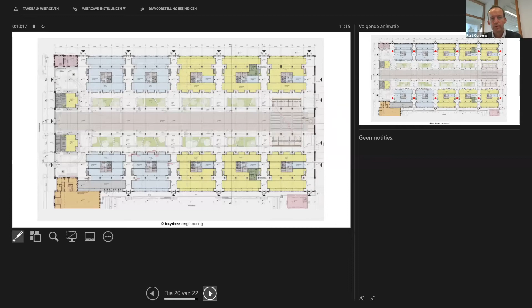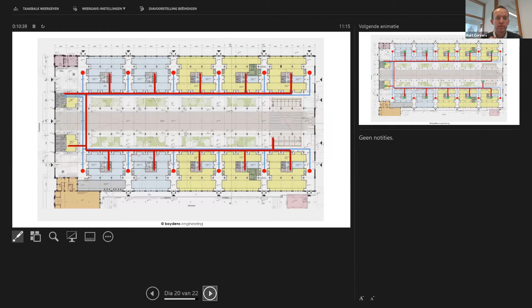How is it laid out in the Gare Maritime? In red we see the geothermal boreholes. This was coupled in a geothermal loop that goes to a central building where there's a heat exchanger, and then the secondary loop distributes the geothermal energy to the different building blocks, where we've got heat pumps integrated in every block. There's also another additional heat pump for what will become a food corner later on.